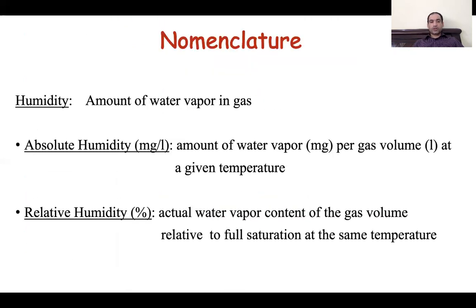Before moving further, we should note certain terms. Humidity is the amount of water vapor present in a gas. It is of two types: absolute humidity and relative humidity. Absolute humidity is the amount of water vapor in milligrams per liter of gas at a given temperature. Relative humidity is the actual amount of water vapor present in the gas relative to the maximum it can hold at that temperature, and is expressed as a percentage.